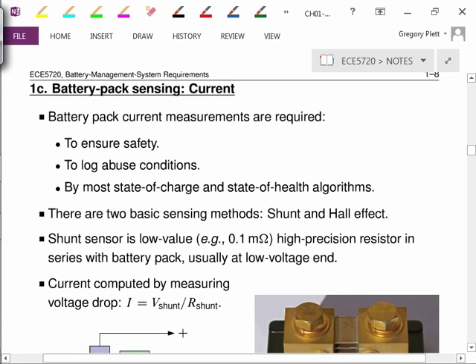In this topic, the last sensing we look at has to do with measuring battery pack current. We have to measure current to ensure safety. There are current limits on cells generally and on the wiring and electronics in the battery management system. So if there's an abuse condition where the load is drawing too much current or trying to charge too quickly, I need to know that so I can shut the battery pack off, or log that something bad has happened for warranty purposes, sometimes diagnostic purposes also. Furthermore, most of the algorithms for controlling the battery pack that estimate state of charge and state of health need to know what the battery pack current is.